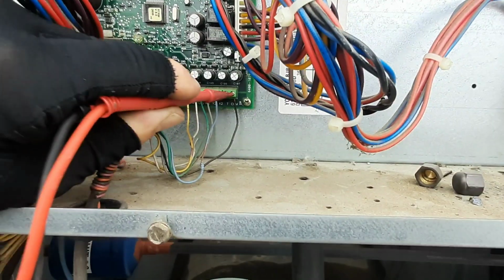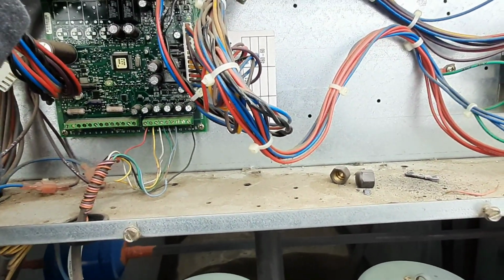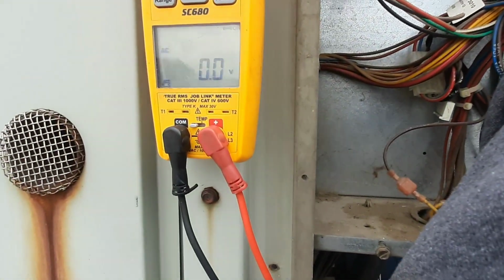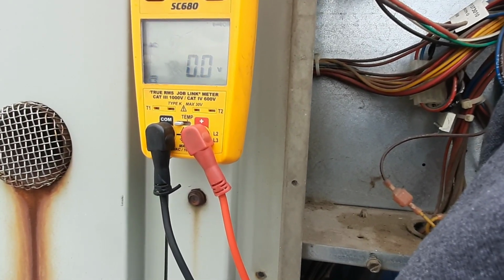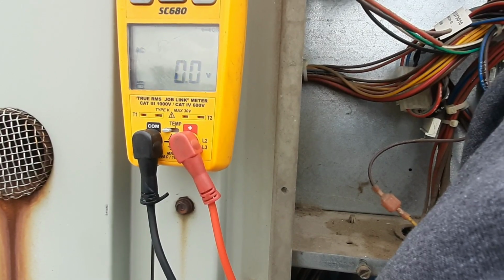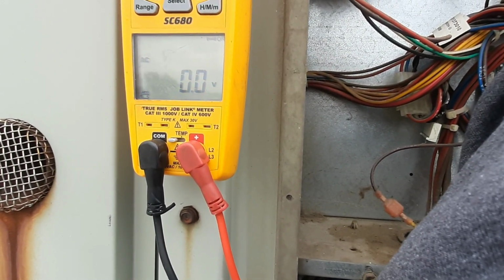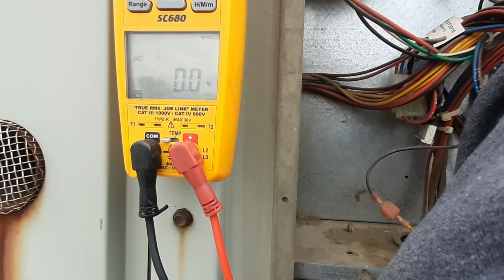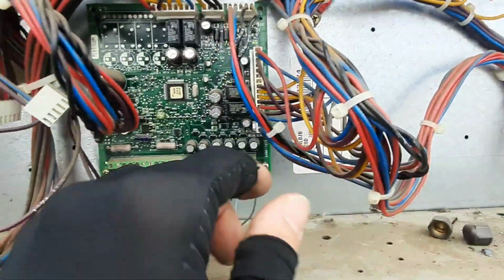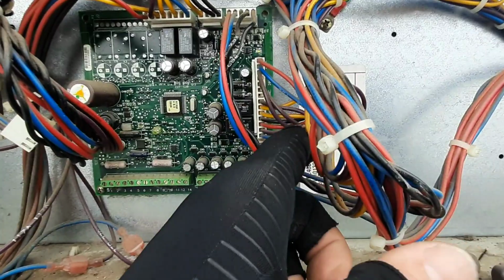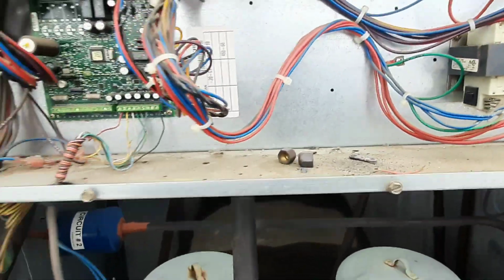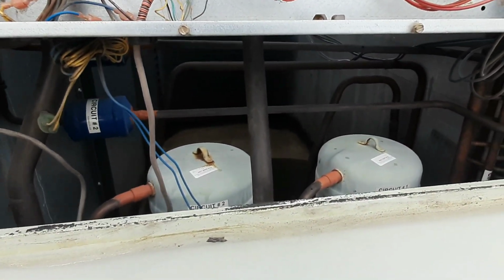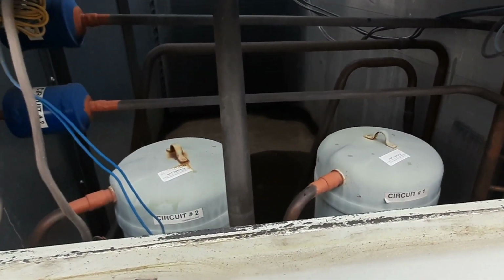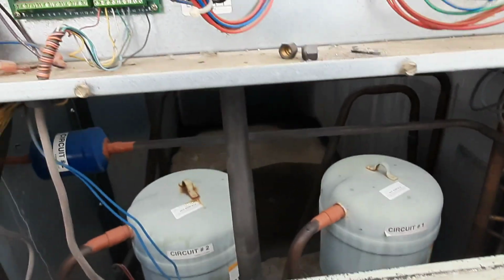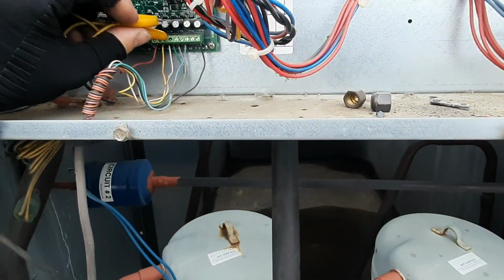So I got no voltage coming from the thermostat. I'm obviously getting voltage here somehow, because my damn contactor's pulling in. One more time. Yep, there's your voltage. I'm getting some kind of voltage from there. Like I said, voltage is gonna come from my RTRM board, which has a lockout right now. Let's do something here. We can jump it out and test if we need to. It's almost got to be that board because the board's not getting a signal from the stat.